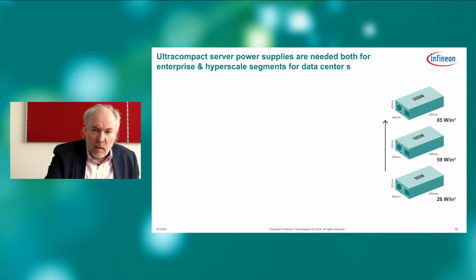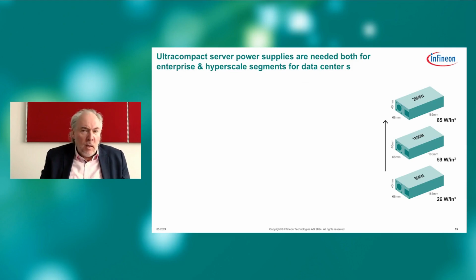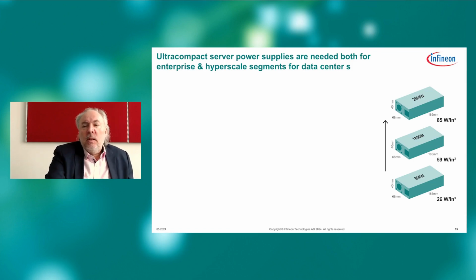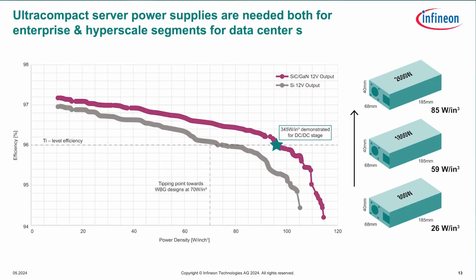Moving forward, we see a continuous increase in power levels, especially in the enterprise segment. As power levels go up and the form factor of the power supply unit is staying constant, we see a constant increase in the power density from 25 watt per cubic inch into 60 watt per cubic inch, achieving 85 watt per cubic inch and above, coming actually close to 100 watt per cubic inch. So in addition, we need to meet 96% efficiency. That is mandatory in Europe, the so-called titanium level efficiency.